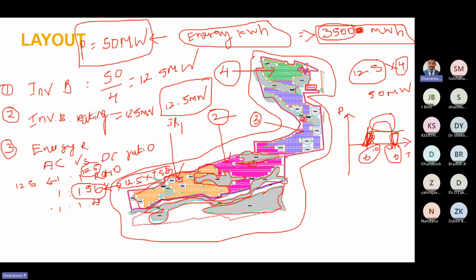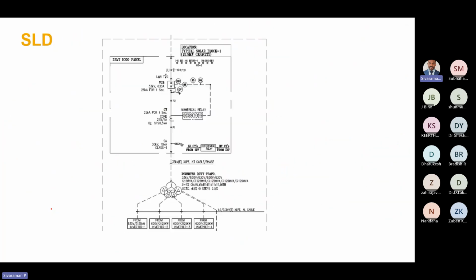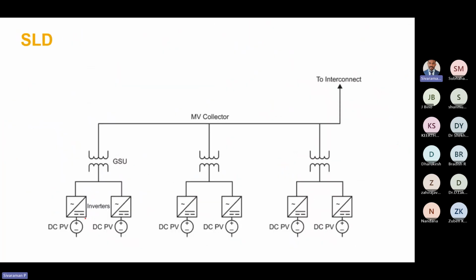This is the very broad way. At a micro level, for designing the PV system, we have to do the calculation for AC cable sizing. How much size of AC cable we are going to use from the inverter to the inverter duty transformer. In this diagram, here an AC cable will come, here an AC cable will come, this will be an AC cable. This sizing we have to do.